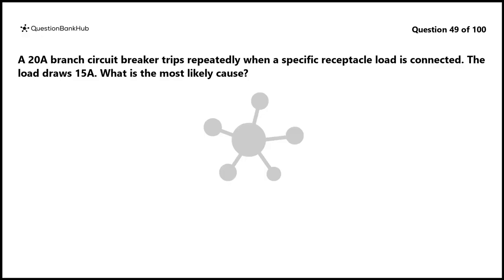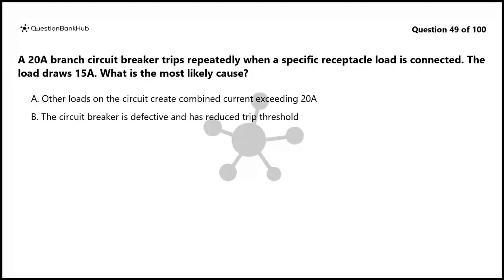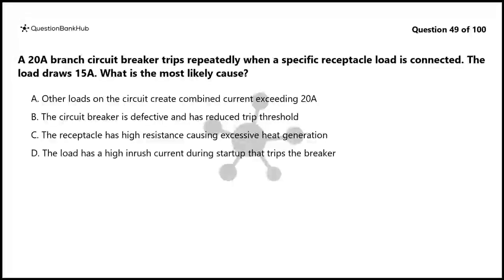Question 49. A 20 amp branch circuit breaker trips repeatedly when a specific receptacle load is connected. The load draws 15 amps. What is the most likely cause? A. Other loads on the circuit create combined current exceeding 20 amps. B. The circuit breaker is defective and has reduced trip threshold. C. The receptacle has high resistance causing excessive heat generation. D. The load has a high inrush current during startup that trips the breaker.